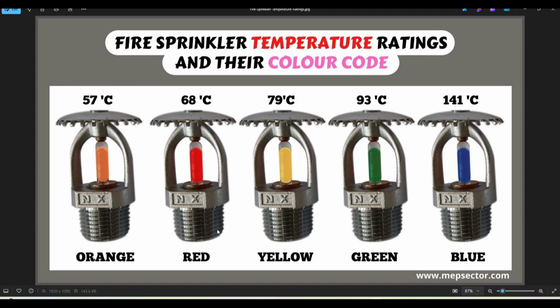When the fire occurs, this plate collects the heat and transfers it to this bulb. The property of the fluid inside this bulb is that when it gets the heat, it starts expanding. When the expansion happens, it breaks the glass, and once the glass is broken, this valve comes out. It is held inside only because of this bulb. So once the bulb breaks, this comes out and it starts spraying the water. Okay, so this is a very simple physical explanation of how the sprinkler works.